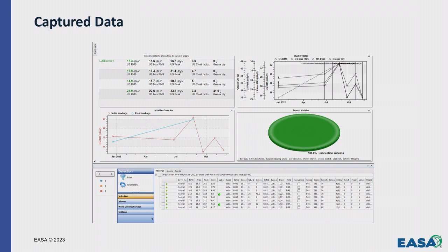The question would be, what is my confidence in this technology versus vibration data? This is a warning sign for vibration data. This does not replace vibration analysis, but it gives an opportunity to put items on a watch list through the ultrasonic data to then share that with the vibration guys. So this is not a solution for vibration analysis, but it gives them an opportunity to catch that thing much earlier and start looking at those potential fault frequencies coming up.